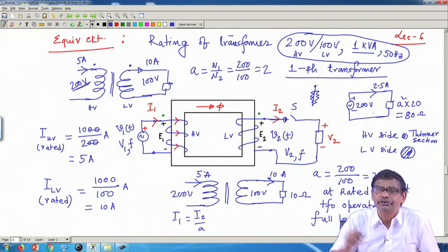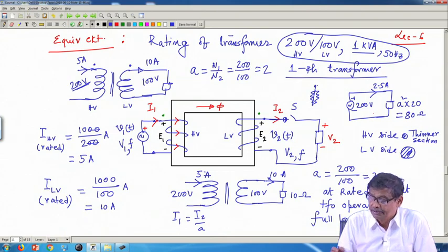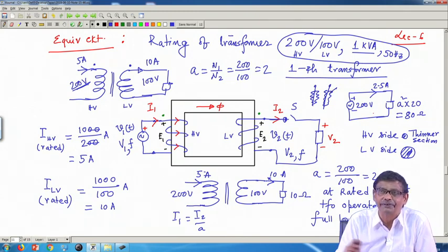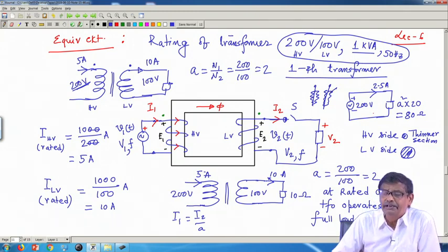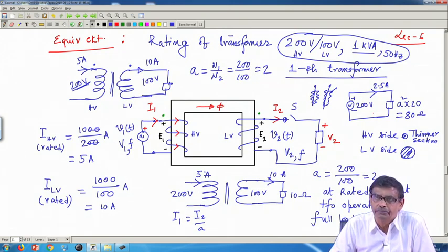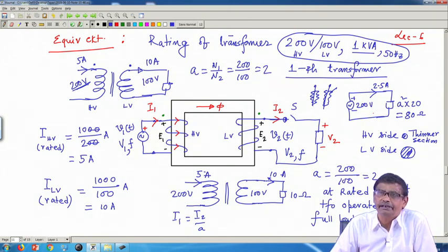You have seen distribution transformer on the roadside, okay, 3-phase transformer. So, these are bushings, these are insulation. Okay. So, insulation level will be decided by the voltage rating of the transformer, and cross sectional area of the copper wire with which you make the coils will be decided by the rated currents of the transformer.